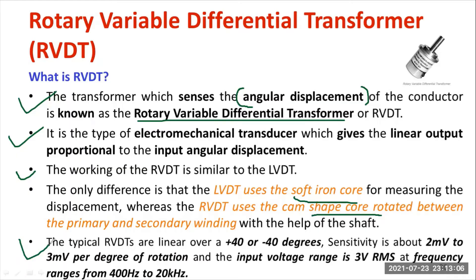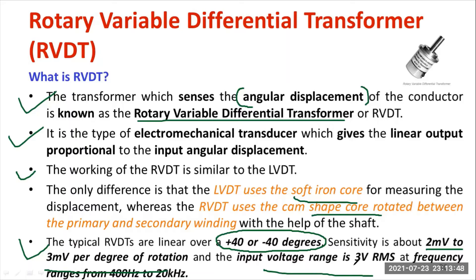Let us understand the specifications of RVDT. RVDTs are mainly used for measurement of angular displacement and they give a linear range over the duration of plus and minus 40 degrees. The sensitivity is 2 millivolts to 3 millivolts per degree of rotation. The input voltage range is 3 volts RMS. The frequency range is in the high frequency range of 400 hertz to 20 kilohertz.